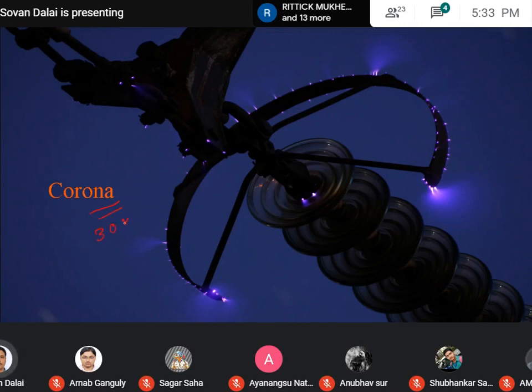Generally, at normal temperature and pressure, if the electric field intensity exceeds 30 kV peak per centimeter, or 3 kV peak per millimeter, in a certain portion, then this phenomenon starts. Suppose you consider a conductor with surrounding air. If the electric field intensity in a certain portion exceeds 30 kV peak per centimeter or 3 kV peak per millimeter, the surrounding air molecules ionize, producing an electron and a positive ion.